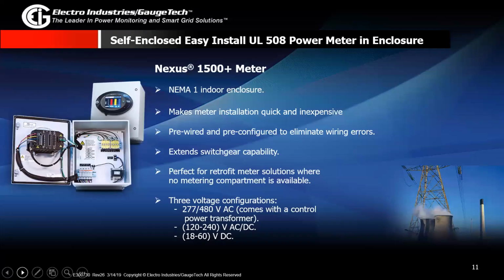This is an example of the 1500 Plus meter. This is very good for easy installation. So we do make these meters in a pre-wired enclosure with the CT shorting blocks, voltage fuses, everything already pre-wired and pre-configured. So this helps in eliminating wiring errors. It's pre-configured from the factory, and you can extend your switchgear capability with this. This is perfect for retrofit metering solutions where there's no separate compartment available for metering. And this is a UL certified 508 indoor NEMA 1 enclosure.